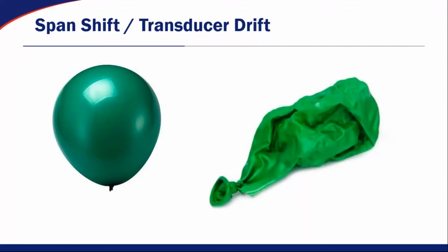Pressure transducers have the same thing happen, whether it's a rubber pressure transducer, plastic, silicon, glass, or some other media, metal that's in there, they all react the same. Depending on the accuracy of the sensor and what it's built with, obviously you're going to have a smaller shift over time, but every single pressure transducer, if you look at the data sheet for it, is going to tell you an accuracy and a span shift year over year.